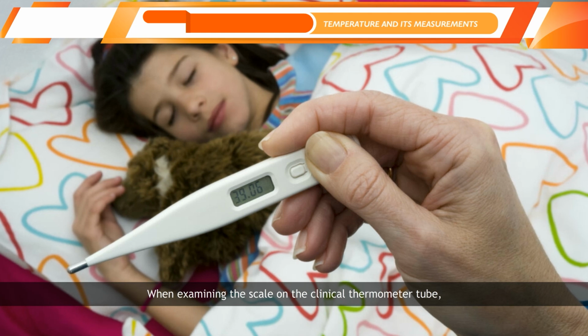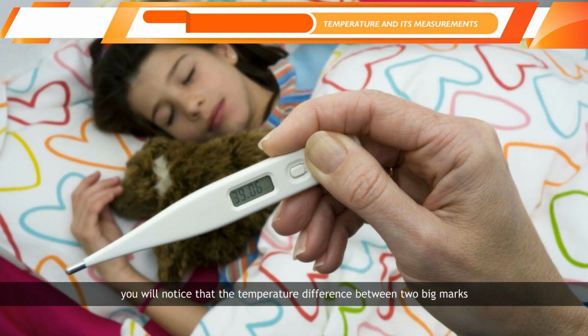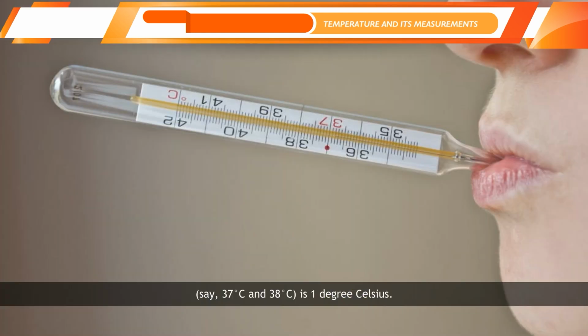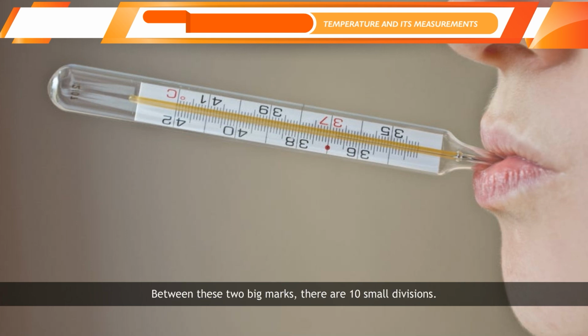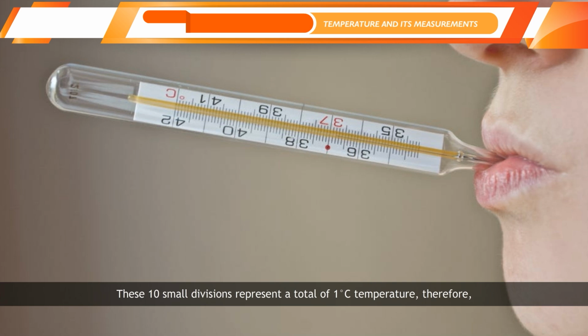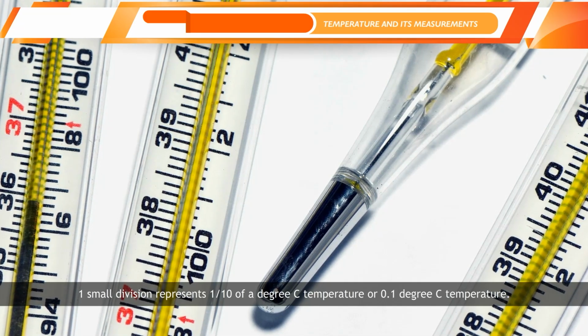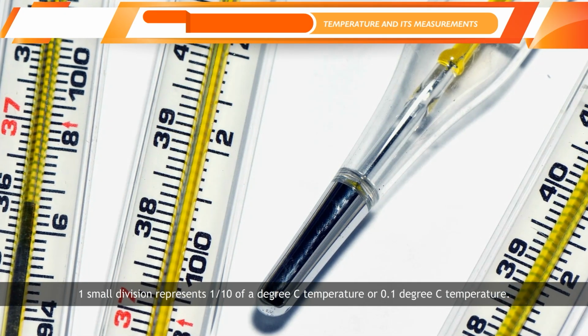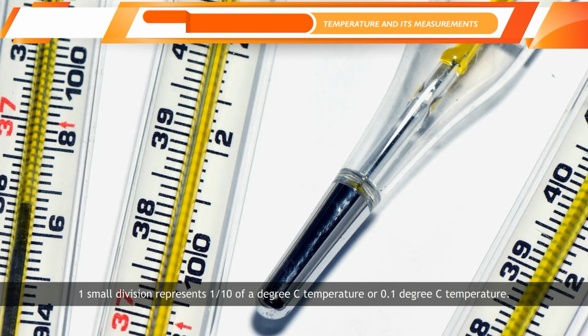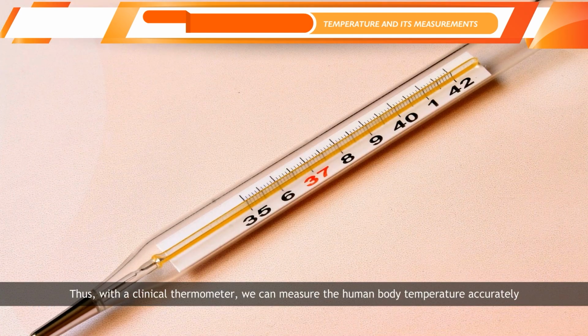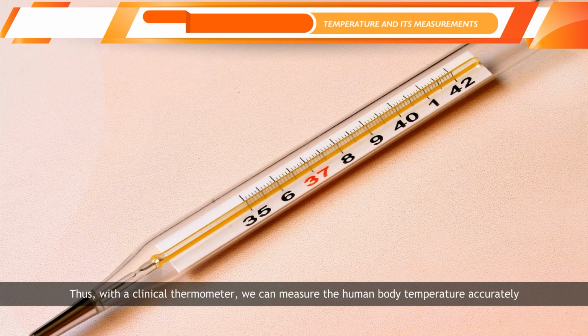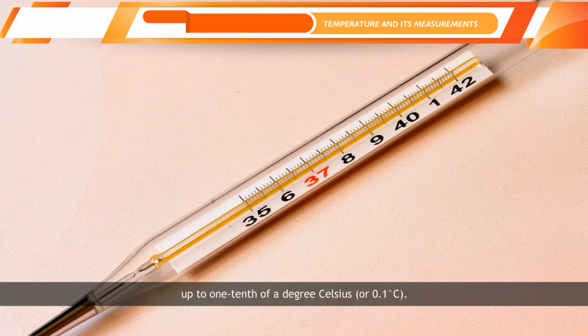When examining the scale on the clinical thermometer tube, you will notice that the temperature difference between two big marks, say 37 degrees Celsius and 38 degrees Celsius, is 1 degree Celsius. Between these two big marks, there are 10 small divisions. These 10 small divisions represent a total of 1 degree Celsius temperature. Therefore, one small division represents 1/10 of a degree Celsius temperature or 0.1 degrees Celsius temperature.